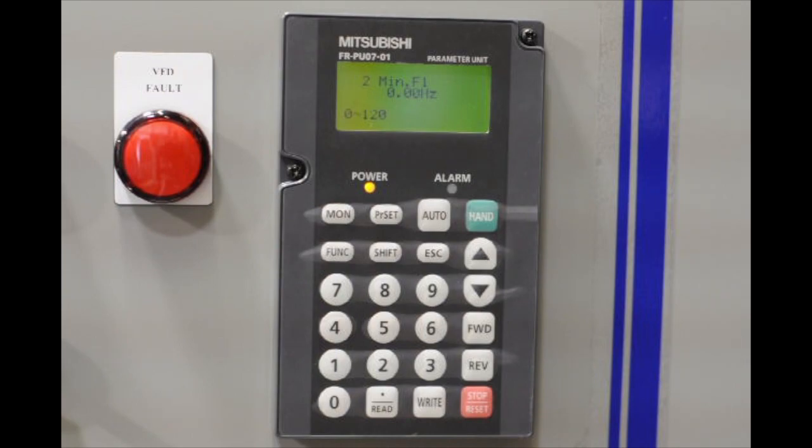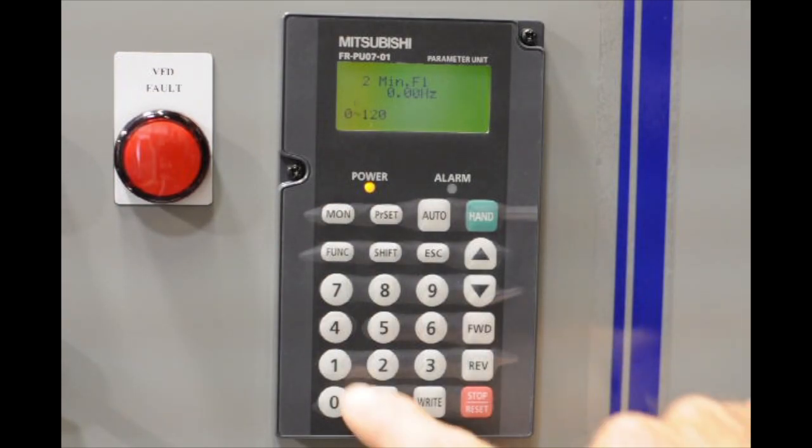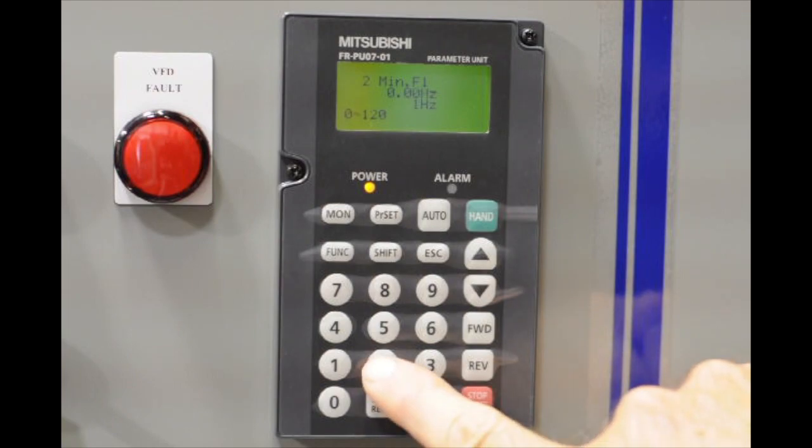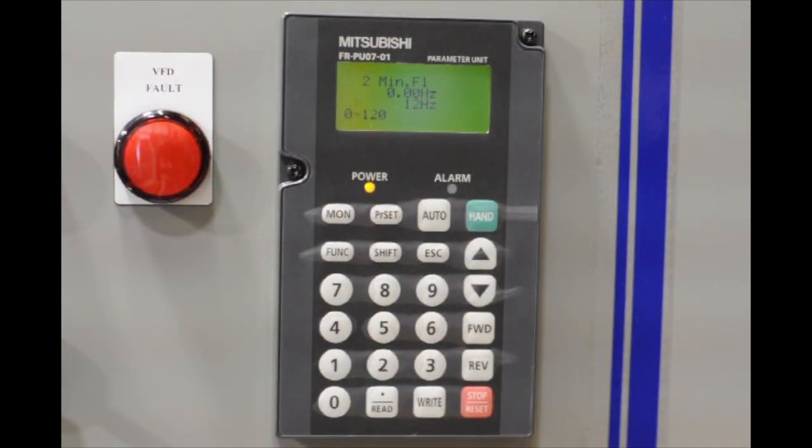Parameter two is the minimum frequency, and in most cases, we usually put a value of 12 as a minimum hertz. So in this case, we'll do that. We're going to type in 12, and we're going to hit write. The VFD acknowledged that by a beep, and the backlight is blinking.